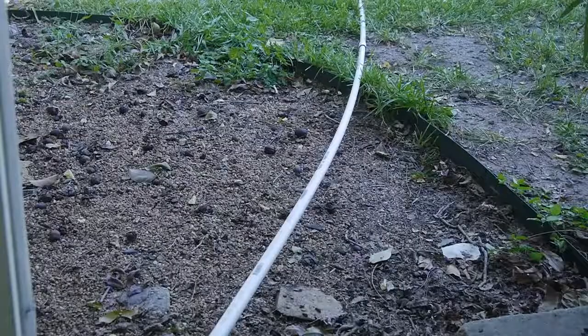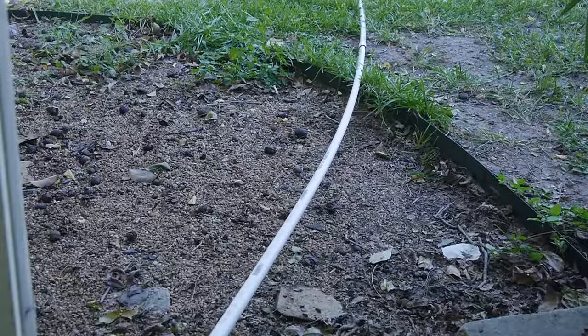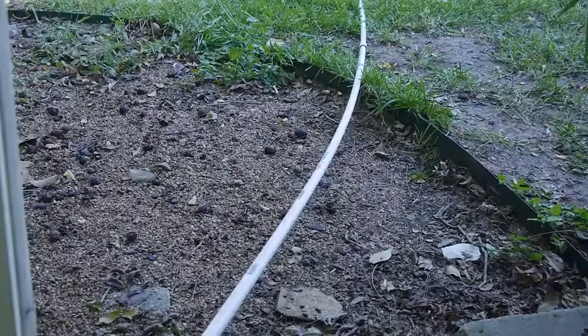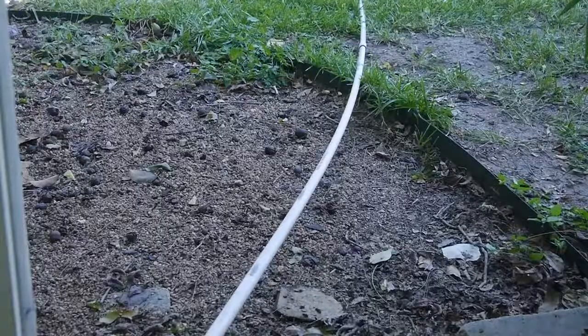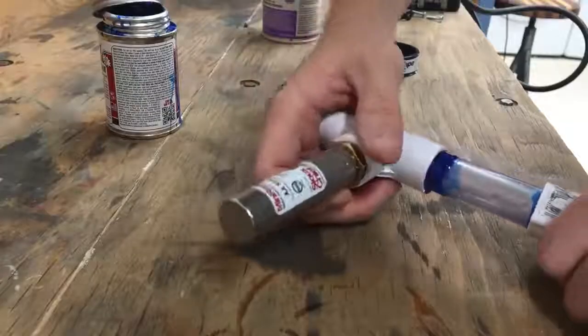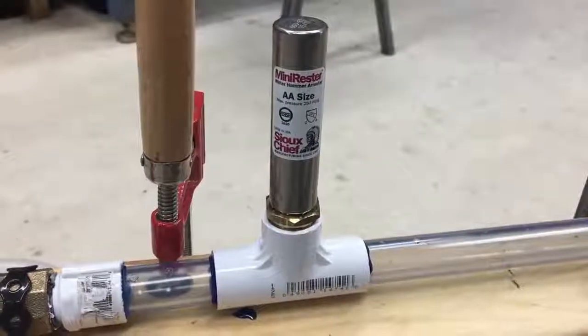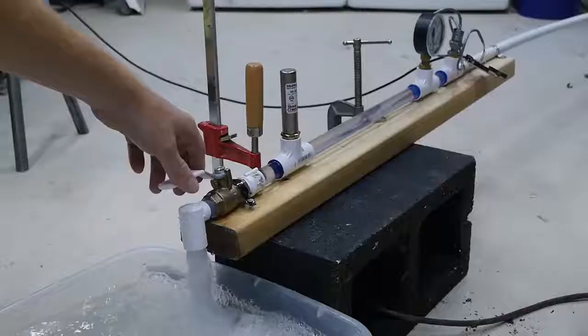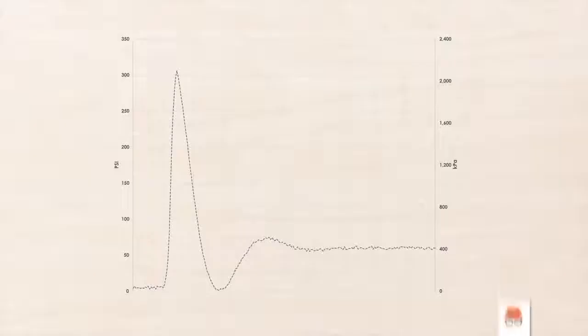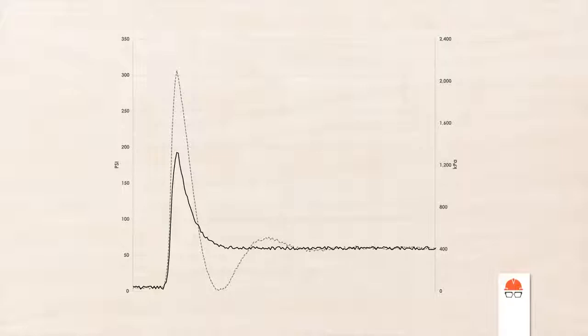In a very rigid system, pressure waves can reflect easily without much attenuation. I've got flexible PVC pipes sitting on the ground free to move, which is already helping reduce the magnitude of the water hammer. I can increase the flexibility even more by adding an anti-surge device. This has an air bladder that can absorb some of the shock and reduce the pressure spike even further.